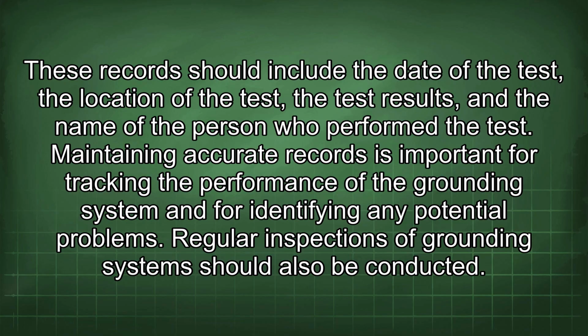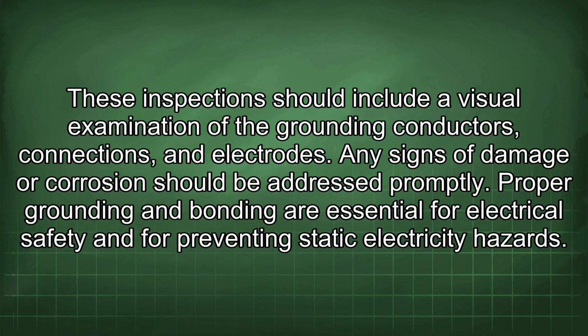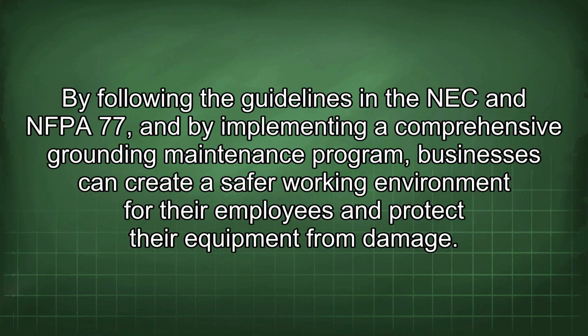Regular inspections of grounding systems should also be conducted. These inspections should include a visual examination of the grounding conductors, connections, and electrodes. Any signs of damage or corrosion should be addressed promptly. Proper grounding and bonding are essential for electrical safety and for preventing static electricity hazards. By following the guidelines in the NEC and NFPA 77, and by implementing a comprehensive grounding maintenance program, businesses can create a safer working environment for their employees and protect their equipment from damage.